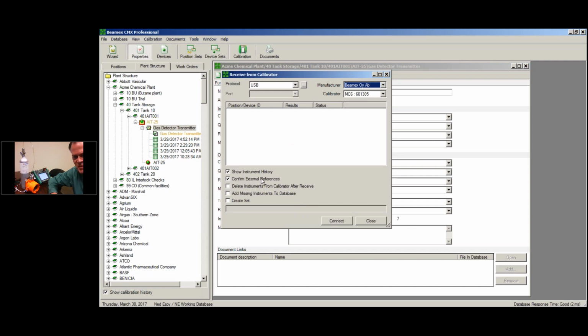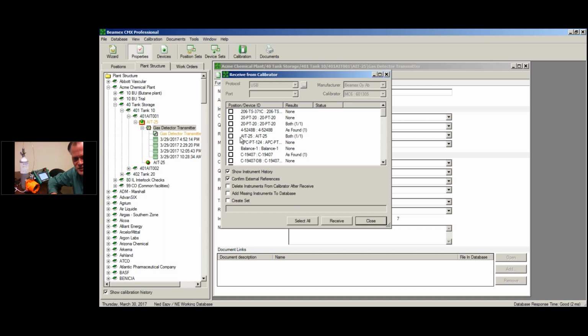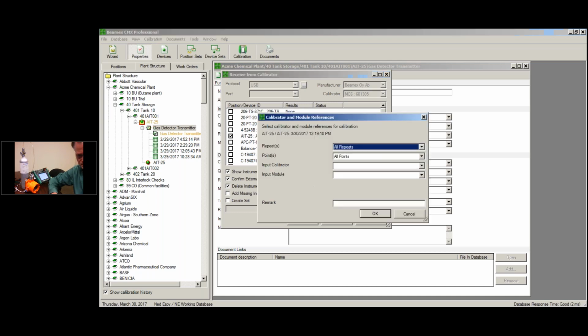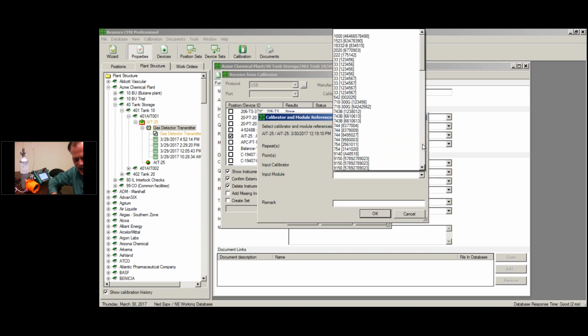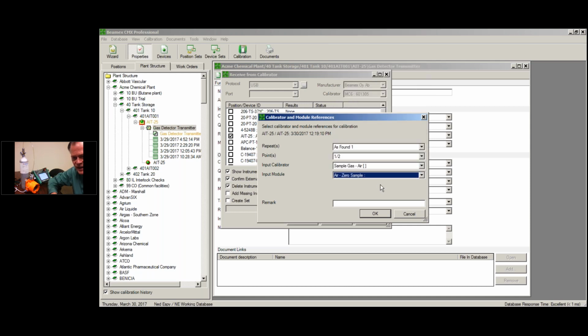And one of the things Roy said is, remember, we need to tell the software what our external references were. So this is a little bit different for CMX. So we're going to first connect to the MC6, and here's the AIT-25 with both an as found, as left. I'm going to leave the other stuff on there, and in fact I'm going to delete this off the calibrator after I receive it. So we're going to pull it in, and just like Roy did, I have to say, for my as found on test point 1, I used ambient air. So here's my air category or calibrator, and then I just note that it's my 0 sample.